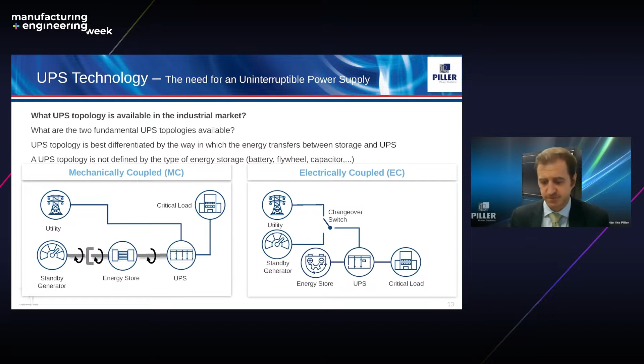Both of these systems offer critical load protection, but sometimes they're best suited to slightly different applications. The conventional static UPS are generally a smaller power device operating at low voltage. They offer a very compact footprint for smaller IT system loads, and they can offer support to larger networks of system loads, but they require multiple machines to be paralleled together.